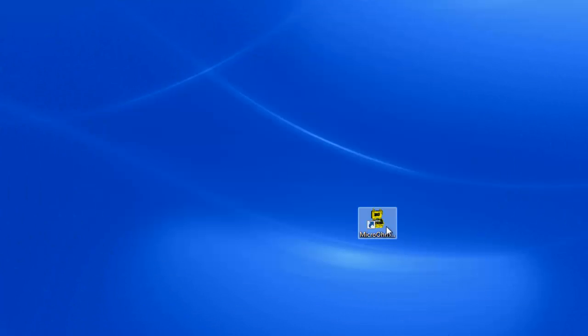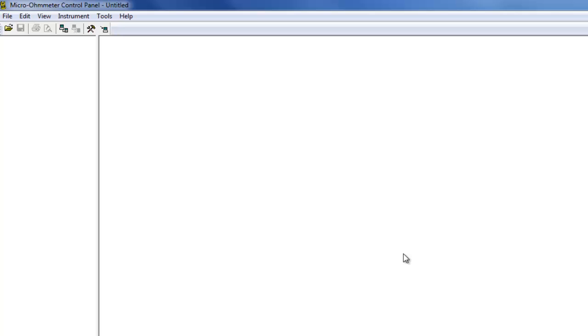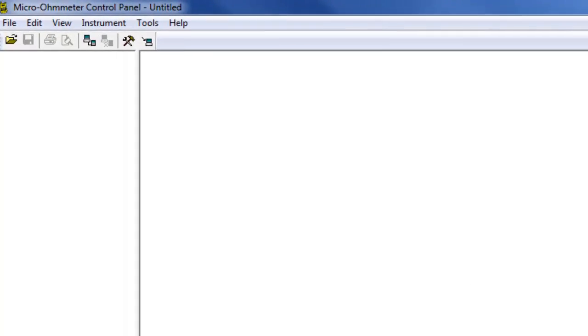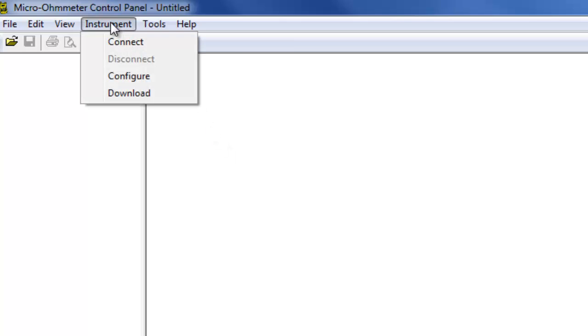To begin the download procedure, open the Micro-Ohmmeter Control Panel by clicking its icon on the desktop. When the Control Panel is open, we can establish a connection between the computer and the Model 6240. To do this, click Instrument in the Control Panel menu bar and then select the Connect option.